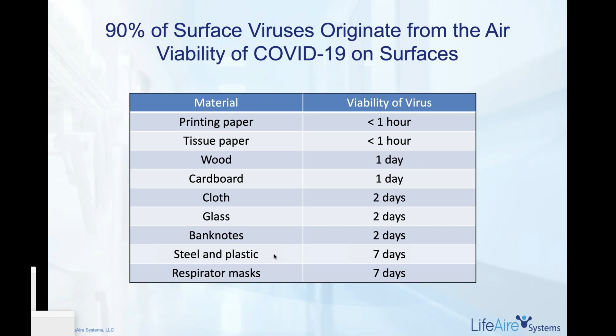So what's available today? There are a number of older technologies that have come back to the surface. For example, there are a large number of in-room units, many using slightly different technologies. But they all have one thing in common, in that they filter the pathogens once the pathogens are already in the space. So the pathogens are therefore already a threat to the occupants. Because the in-room unit is not filtering the air entering the space through the HVAC system, you can have infectious pathogens enter the space you're trying to protect via the ductwork or the air handler in your building.